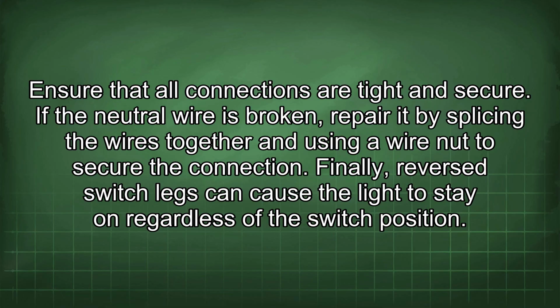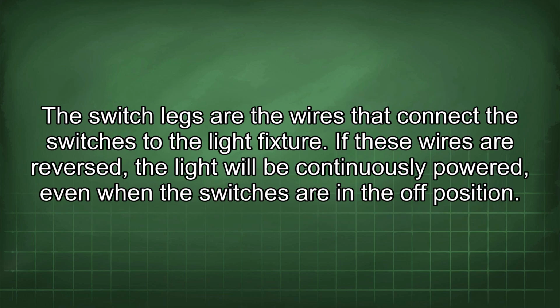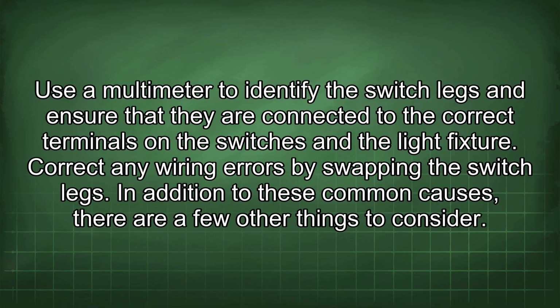Finally, reverse switch legs can cause the light to stay on regardless of the switch position. The switch legs are the wires that connect the switches to the light fixture. If these wires are reversed, the light will be continuously powered, even when the switches are in the off position. Use a multimeter to identify the switch legs and ensure that they are connected to the correct terminals on the switches and the light fixture. Correct any wiring errors by swapping the switch legs.